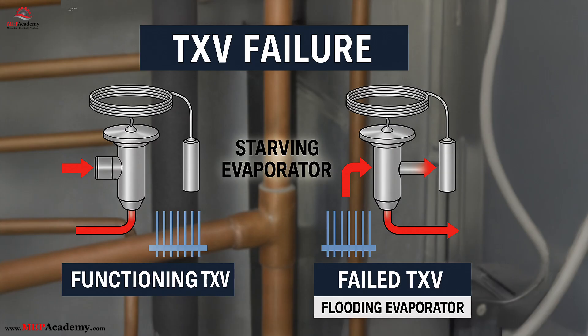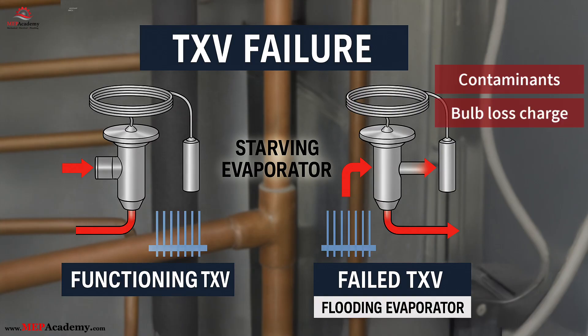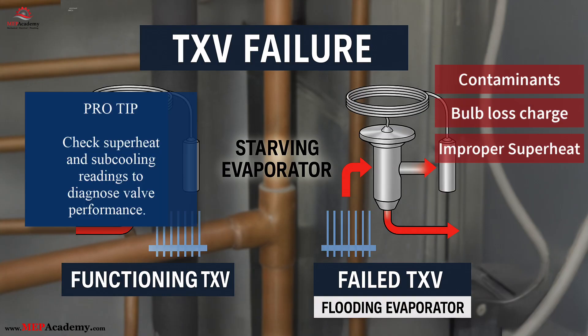Number two: The thermostatic expansion valve, or TXV, regulates the flow of refrigerant into the evaporator. When it fails, it can either starve the evaporator, leading to high superheat, or flood it, which risks damaging the compressor. Common causes: contaminants blocking the orifice, bulb sensing line losing charge, or overtightened superheat adjustment. Pro tip: check superheat and sub-cooling readings to diagnose valve performance.